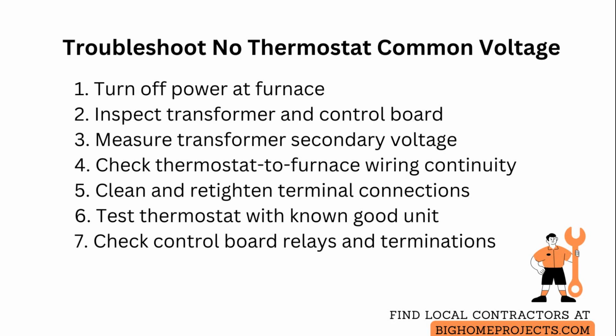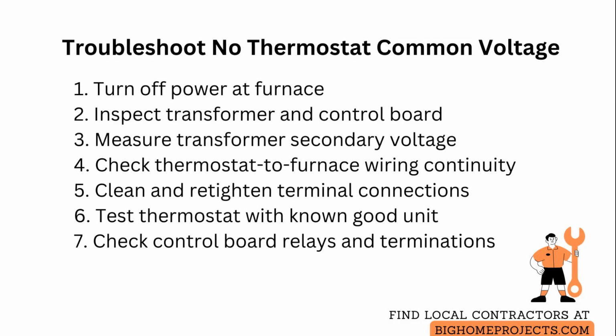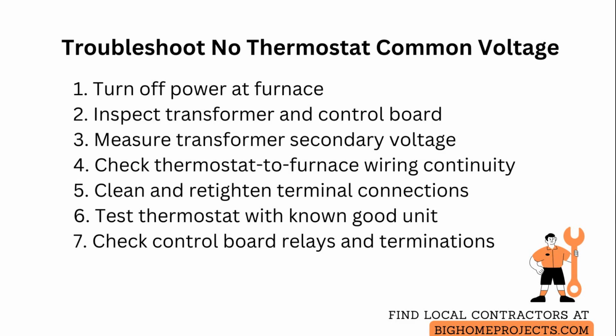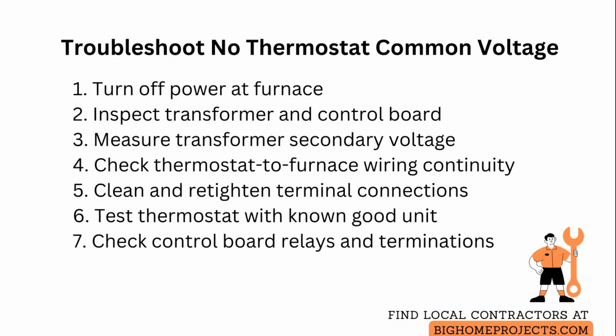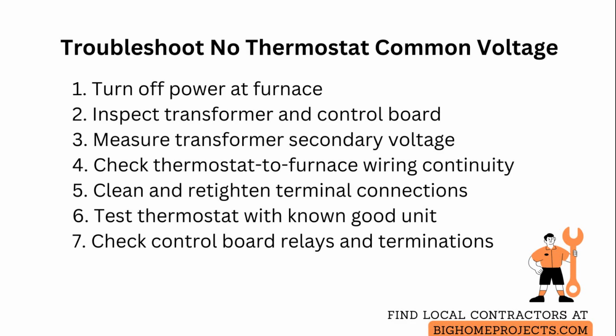Next, with power restored, measure the transformer's secondary output across its 2 low voltage terminals. A healthy transformer will show approximately 24 volts alternating current, and a significantly lower reading or 0 indicates a failed transformer that must be replaced.